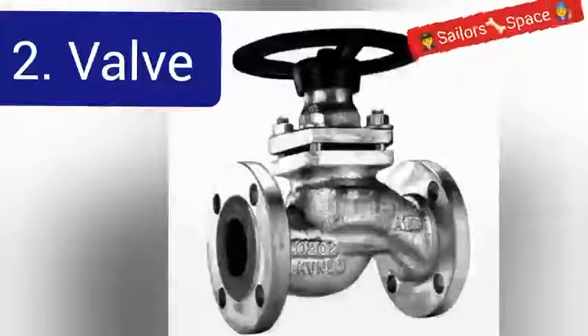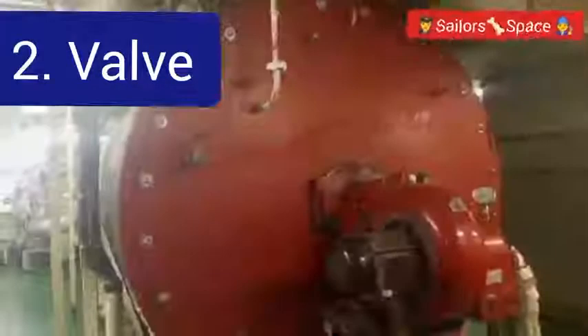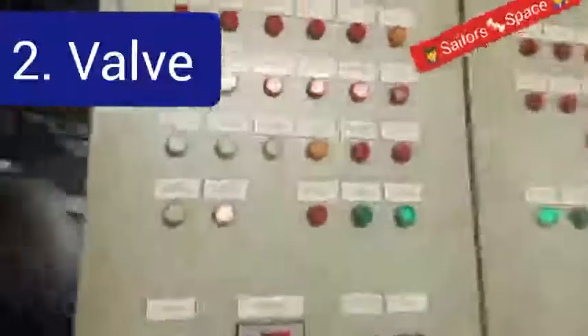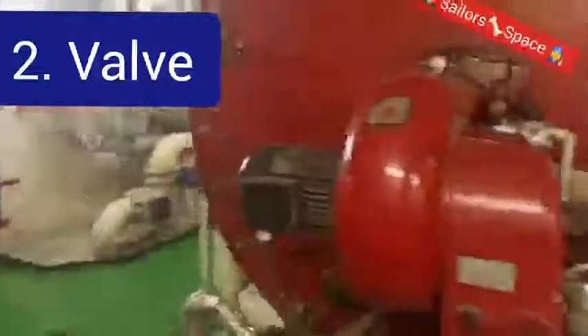It is recommended that air-cooled mechanical seal pumps or water-cooled pumps be used. The second component is the valve. When fluids are to be transferred, there must be a control process to allow fluid in and out. Since this system involves very high temperatures, the valve construction must be very strong and leak-proof. Bellow-type seal valves are recommended for the thermal fluid boiler system, as they ensure full closure and withstand wear that develops in the material over time.